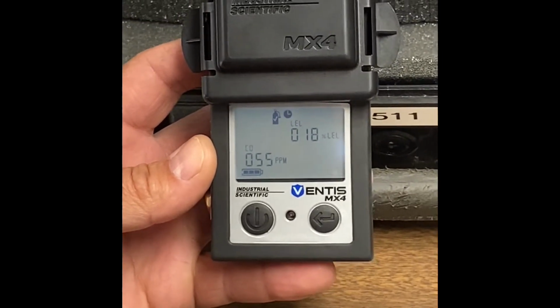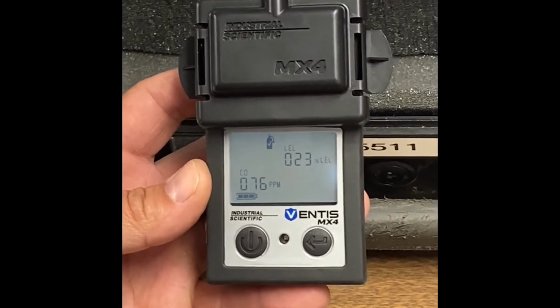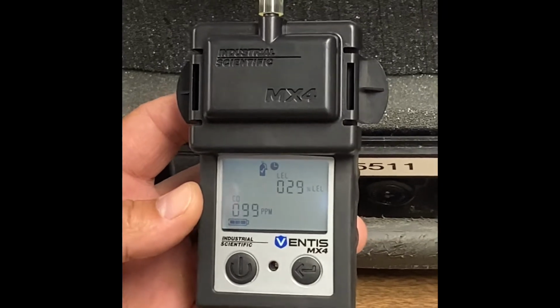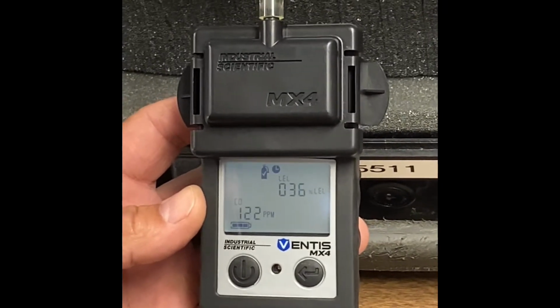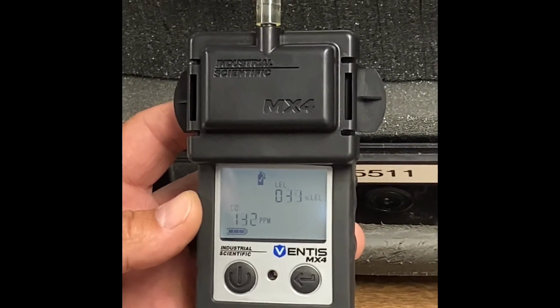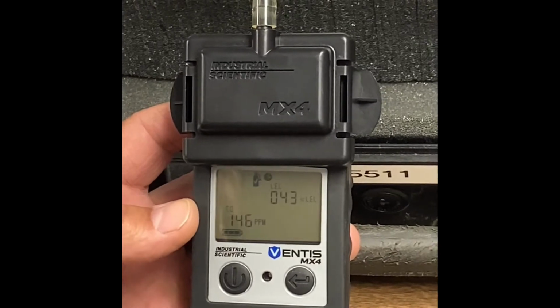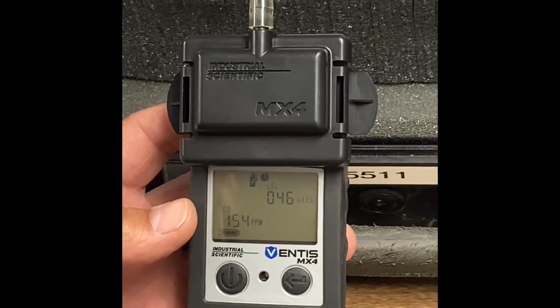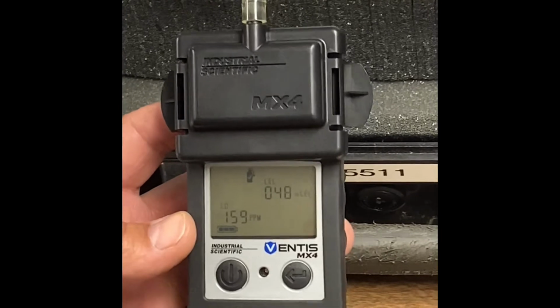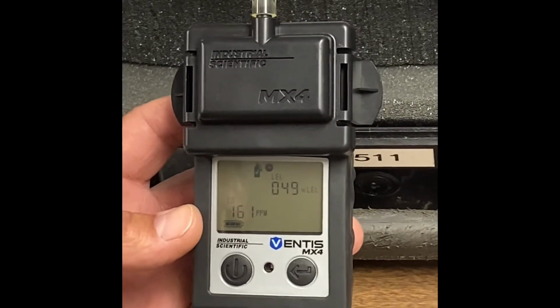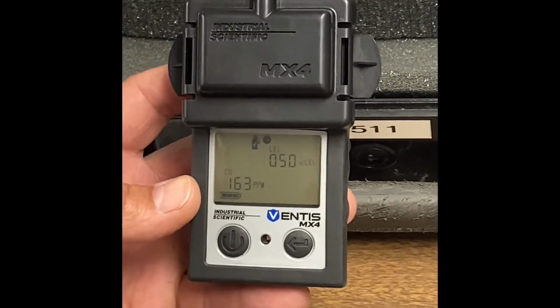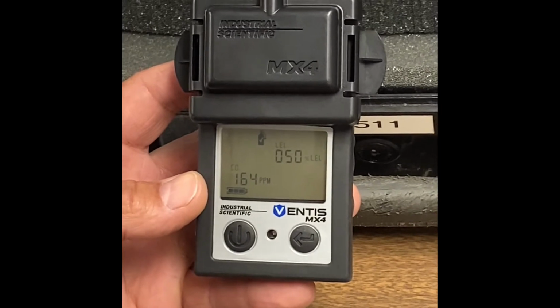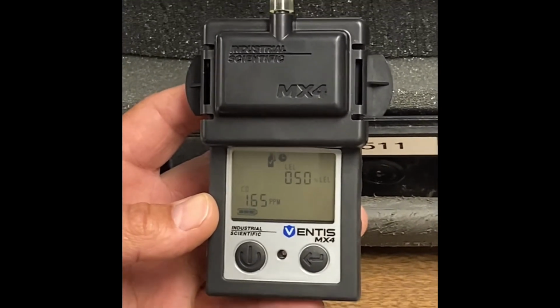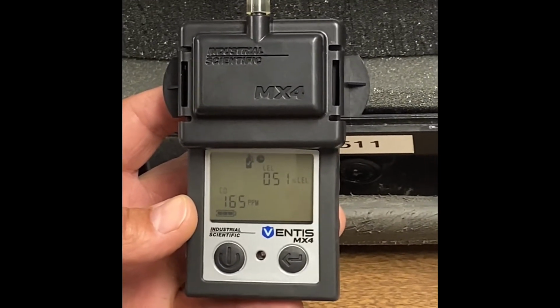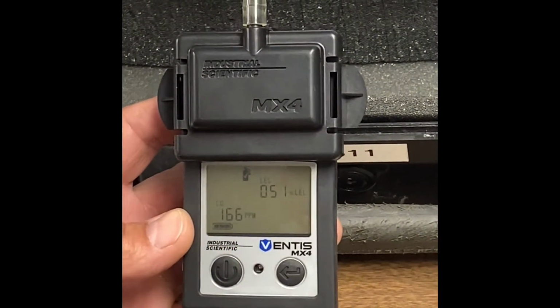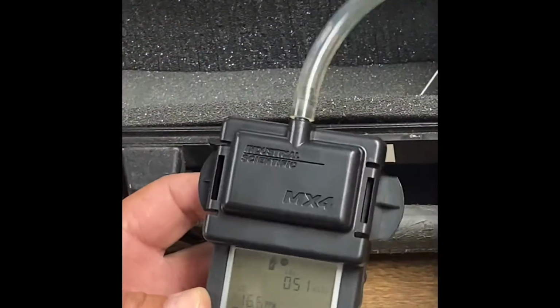These numbers will go up. What you also want to make sure you have is a piece of paper to write down the numbers, because they flash very quickly and then end up going away, and they only appear twice after the calibration is completed. So make sure you note the numbers. You'll actually have 3 numbers toward the end of calibration that you need to note, but you'll see the flashing, and you're going to see the number.